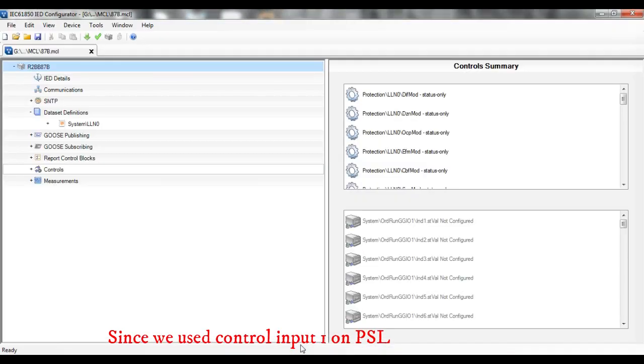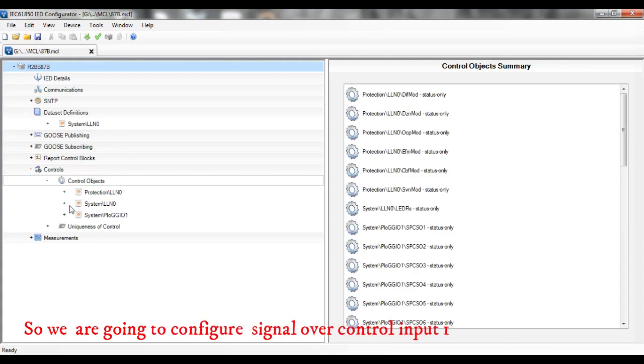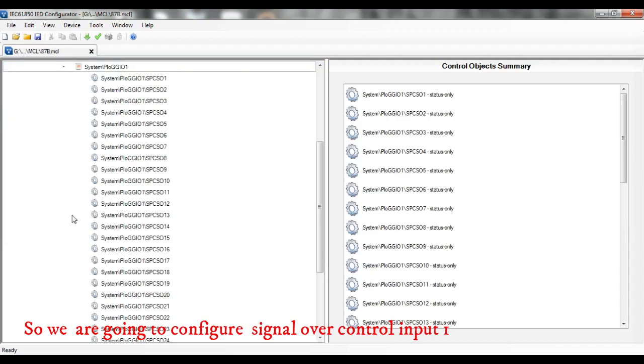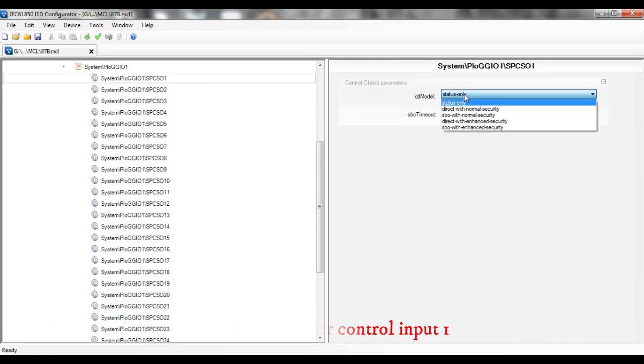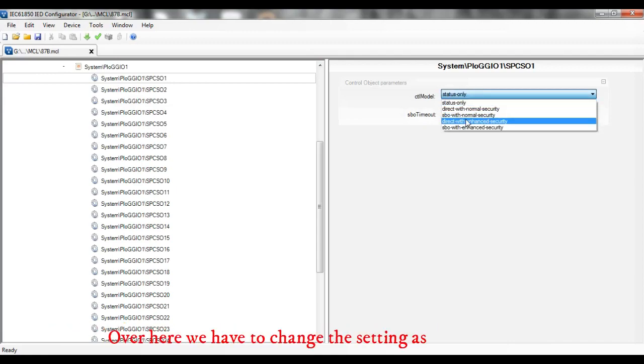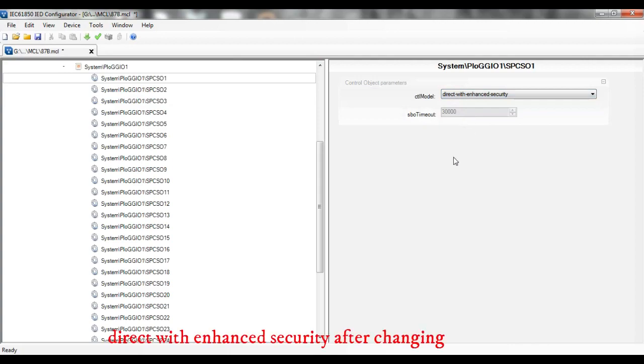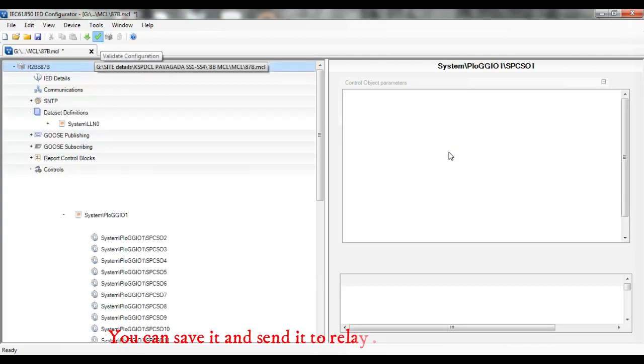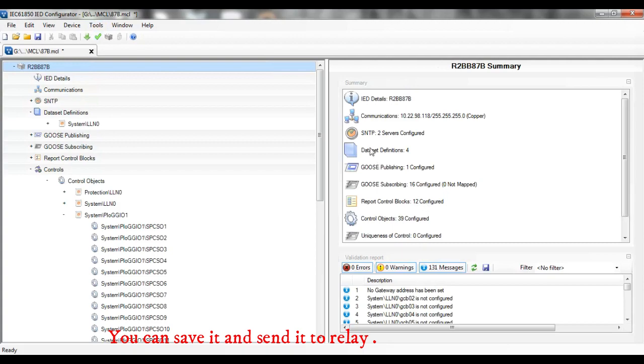Since we used control input 1 on PSL, we are going to configure the signal over control input 1. Over here we have to change the setting to direct with enhanced security. After saving, you can save it and send it to the relay. Now this signal will work for your command.